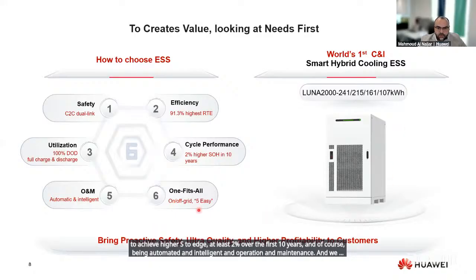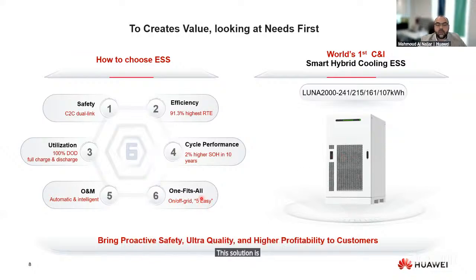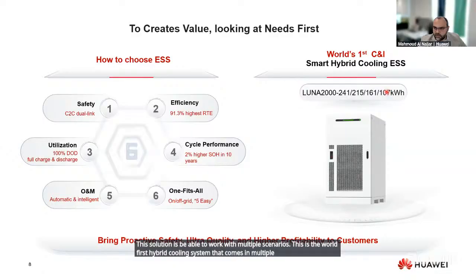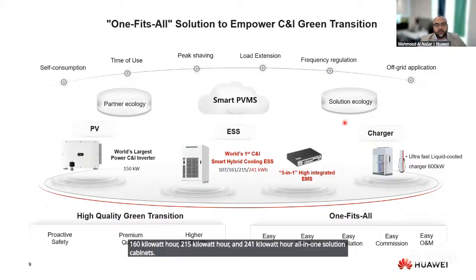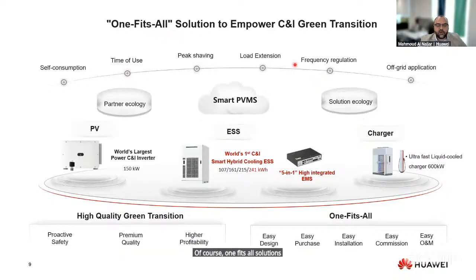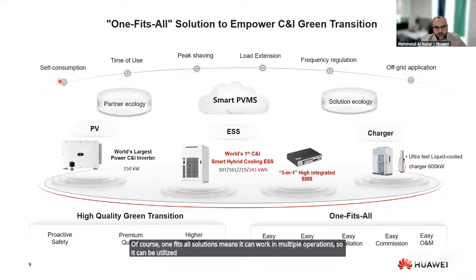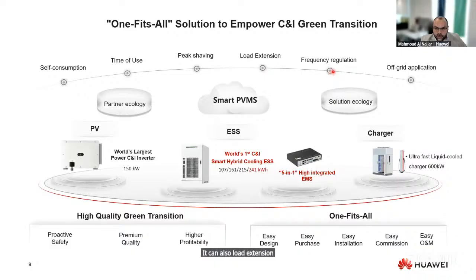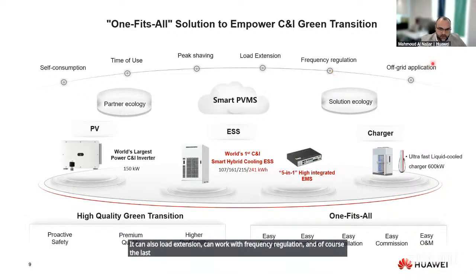And we have designed this solution to be one fits all, meaning this solution is able to work in multiple scenarios. This is the world's first hybrid cooling system that comes in multiple sizes: 107 kilowatt hour, 161 kilowatt hour, 215 kilowatt hour, and 241 kilowatt hour, all in one solution cabinets. Of course, one fits all means it can work in multiple operations. So it can be utilized in self-consumption scenarios, time of use, and these are on-grid applications. Of course, time of use, peak shaving. It can also do load extension, can work with frequency regulation, and of course, the last one is to work completely off the grid.